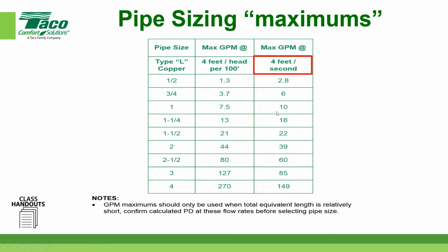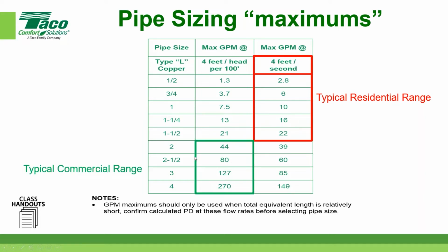And everybody knows that those are generally the Taco 0013 or Grundfos 2699, et cetera. What we want to try to do is design our systems at smaller circulator sizes, so the end user, the building owner, doesn't experience the additional expenses involved in that. So anyway, let's move on. Again, I talked about this in ranges, right? The ranges go to 1.5 inches, typically stay with the 4 feet per second and 2 feet per second rule. And when you get over to 2 inch, 2.5, 3, 4, all the way up from there, that's typically commercial. This is your ASHRAE number. This is your modern hydronics number. So just think of it that way. Hope that helps.